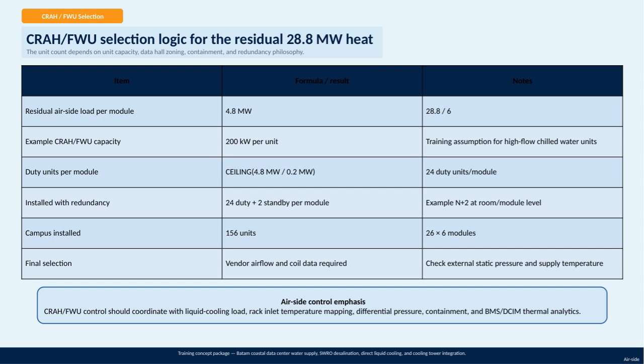On the air side, the calculation for residual load per module is 4.8 megawatts, which is simply the total 28.8 divided across 6 modules. For the high-flow chilled water units, we assume capacity of 200 kilowatts each. This means each module requires 24 duty units. That's 4.8 megawatts divided by 0.2 megawatts per unit. To ensure reliability, we add redundancy at the room or module level, following an N+2 approach. So, for each module, 24 units are active and 2 are on standby, bringing the total to 26 units per module across the entire campus. That sums up to 156 units.